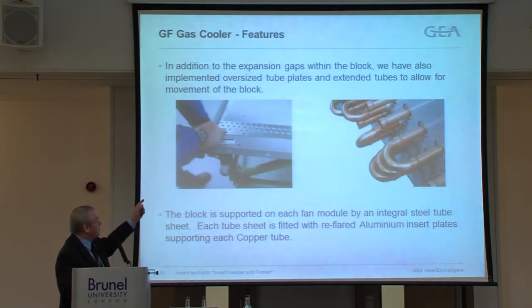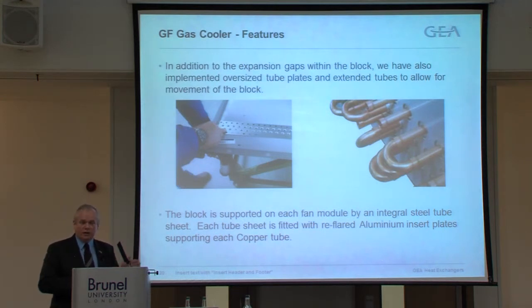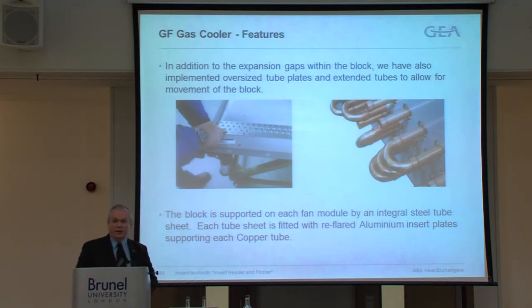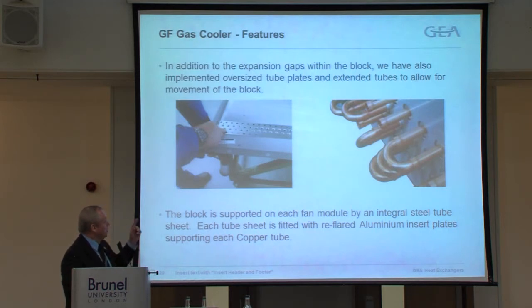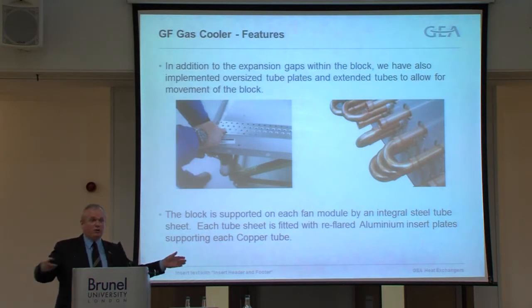The fan plates have aluminium inserts in them. So every fan plate that goes through that unit on the 1200 through to the 2.1 has got this aluminium plate in there. And the idea there is that as the tube expands and contracts, it's actually sliding on the aluminium. The aluminium is considerably softer than the copper, therefore we're eliminating any possibility of leaks on the matrix. On the larger B modules, C modules and D modules, we have an extra sheet that goes in the middle of the fan plate as well.